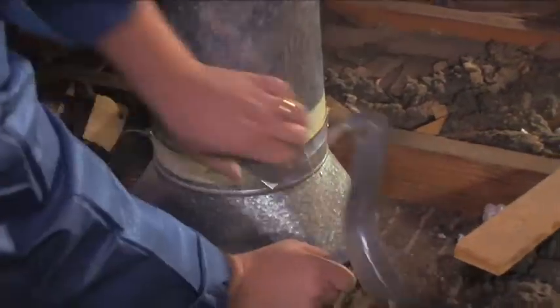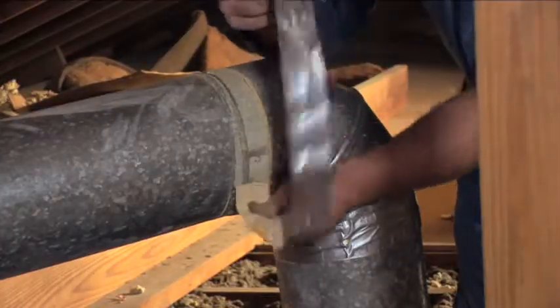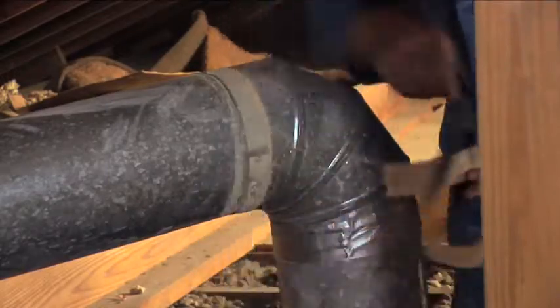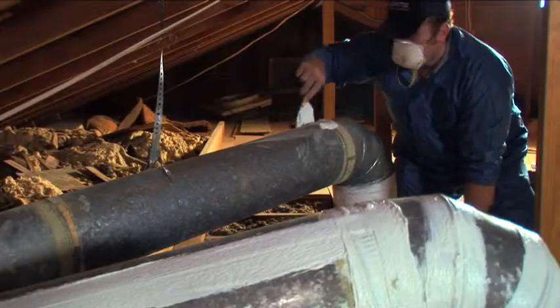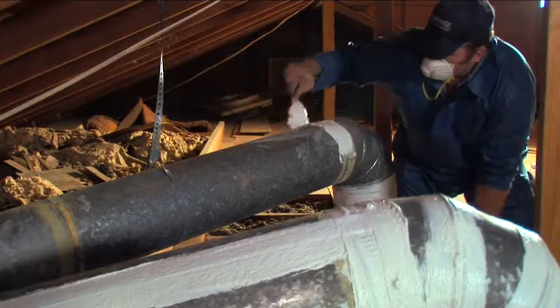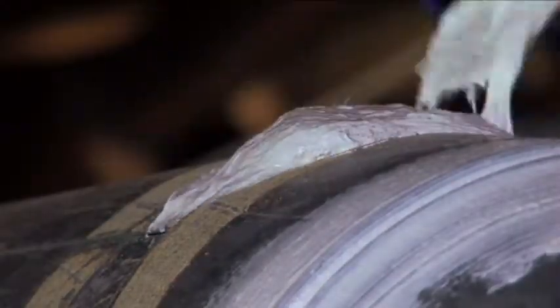One reason is that the standard duct tape historically used to seal the joints dries out and doesn't last. So we looked at every product that was sold to seal ducts to see how well it worked. And pretty much all of them worked well if used as applied, except one product, and that product was duct tape. Today, good contractors use fiber-reinforced elastomeric duct sealants. This provides a permanent fix that won't peel off over time. Many systems were actually put together with no sealant of any kind.